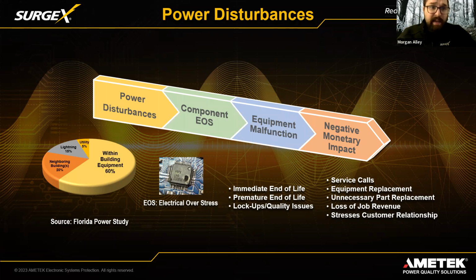In terms of day-to-day operations, where power really affects what you're doing and interacting with your technology daily, that's lockups and quality issues. I'll go into a job site and ask a simple question: do you have any problems with power? Most of the time somebody flicks a light switch on and off and says, nope, see, my light works. They don't understand the nuance that a dirty grid or dirty power supply is actually causing to their equipment. So the most common problem we face is lockups.